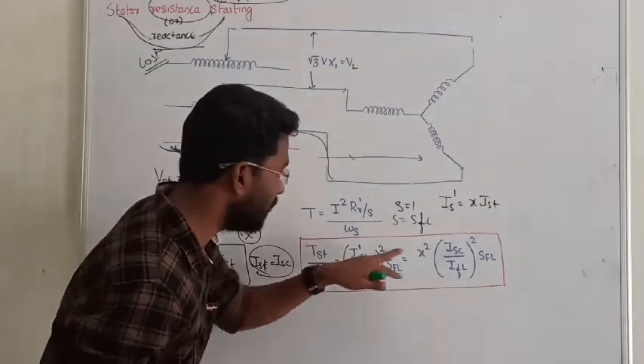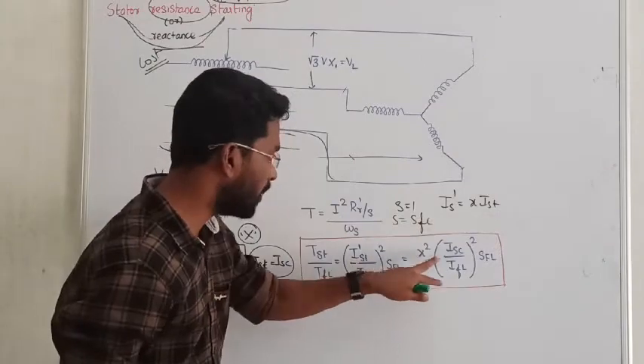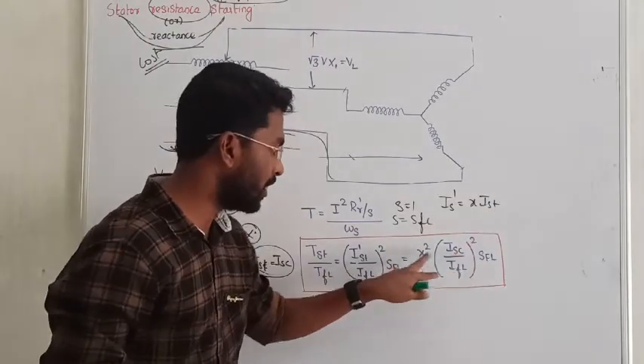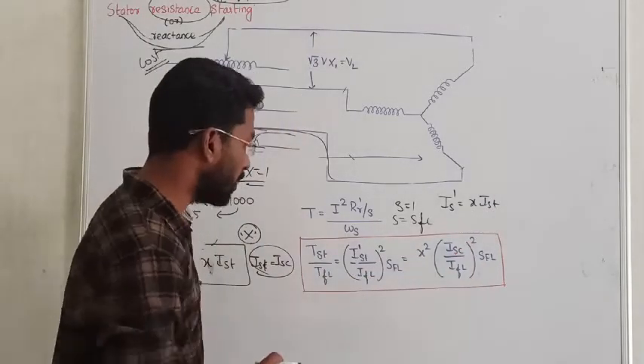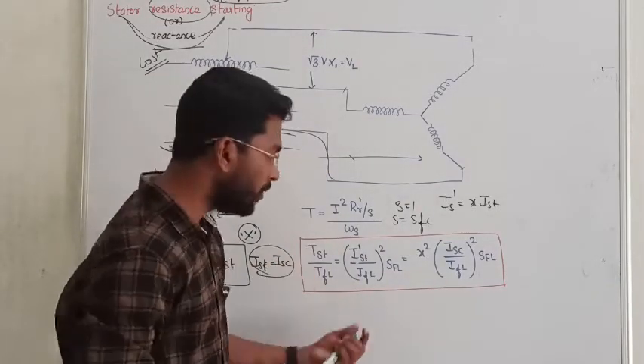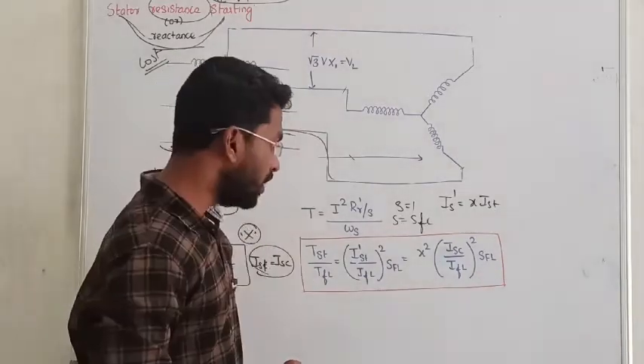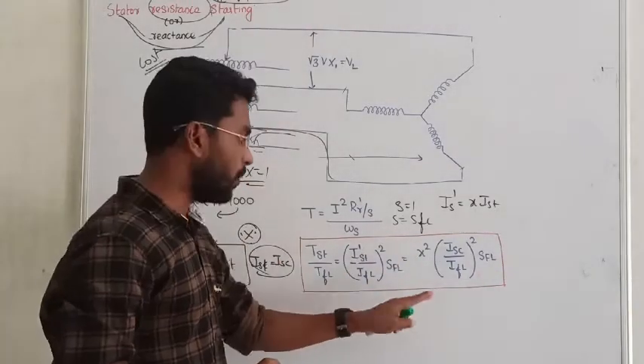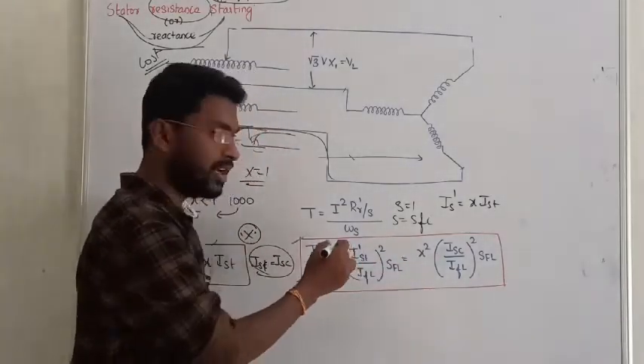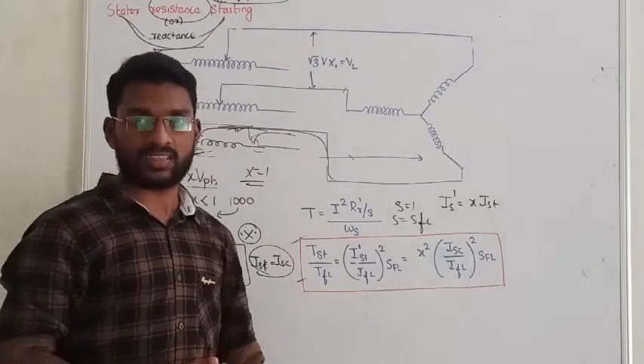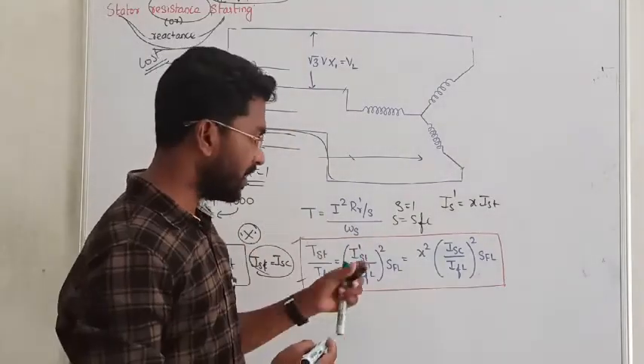Since the starting current is X times the actual short circuit current, the starting torque becomes X² times the actual starting torque. That is how we control the starting current and the torque-to-starting relation in the case of Stator Resistance or Stator Reactance starting method. This is all about the Reduced Voltage Method. You can ask questions in the comment section. Thanks for watching.